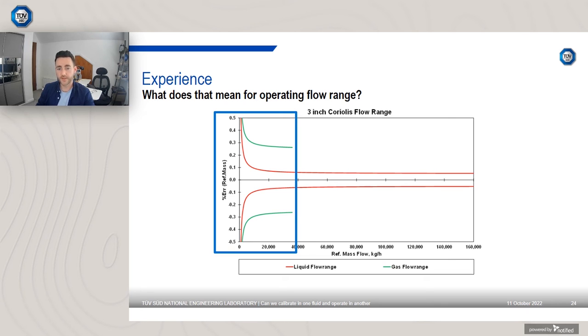I would then, calibrating in liquid, aim to also calibrate it from 10 to 90% of the liquid mass flow rate, the liquid flow rate range. That then gives you both the same flow rates being matched with respect to kilograms per hour mass flow rate, but also with respect to turn down. So I'd have confidence in the meter performing across its turn down range, but also crucially I'd have confidence in it performing with respect to the exact same mass flow rates. So that's two things to be aware of there.